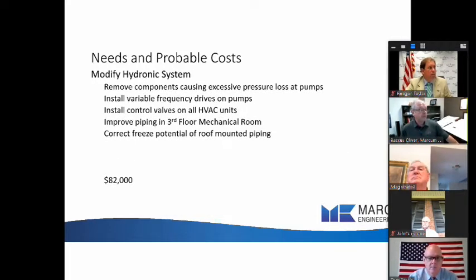Next, I would modify the hydronic system. I would remove the components causing excessive pressure loss. I would install variable frequency drives on the pumps and slow them down to pump only as much as needed. This means I would install control valves on all your HVAC units throughout the building. Those control valves are needed to shut off water to them when it's not needed. That's what allows the pump to be slowed down. I would improve the plumbing on the third floor mechanical room, and I would correct the freeze potential of the roof mounted piping. I don't think we faced that the last couple of years, but it has been a problem in the past. All in all, this would be $82,000. Just one whole number for that improvement.